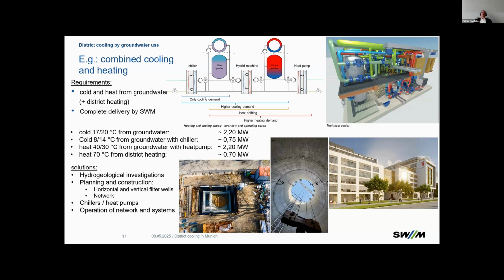That is, when you have, for example, a data center in the building, which every time produces heat, also during winter time, we move that heat to the other side where it's needed, for example, for heating the building in the winter time. And we do the same thing to the other side during summer when cooling is needed. So it's a very interesting combined system. And it's been running for several years and we have very good data from it.